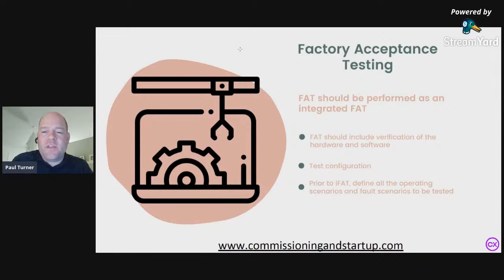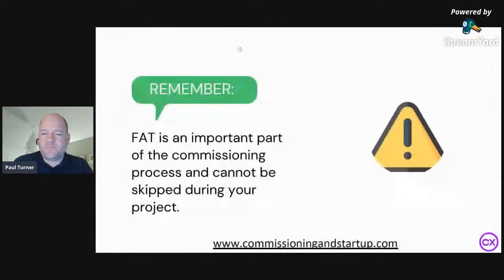I've seen that cause nothing but problems, and I strongly discourage that. Having a properly planned upfront factory acceptance test where you test both the hardware and the software will always save the project several cost and schedule impacts. I need to stress the importance of doing an integrated factory acceptance test.